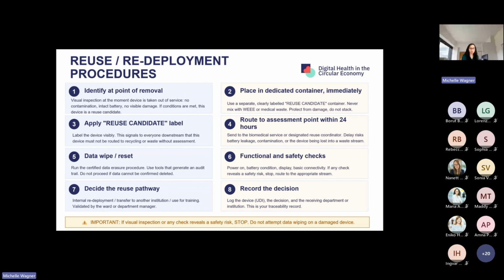One practical point I'd like to emphasize is labeling. Labeling might seem like a minor administrative task, but in reality, it's a communication tool. A clearly labeled device that says, for example, reuse candidate, immediately tells everyone who handles it that it needs to be assessed for reuse instead of just being disposed of. Without that label, the device may simply be treated as waste, right? Another important point is timing. The longer the device remains in temporary storage, the greater the risk of physical damage, battery deterioration, contamination, or simply that it becomes forgotten. So of course, any device can potentially be reused, but there are two essential questions that still need to be answered. Is it safe? And does it still contain patient data? Does it also obey the legal requirements?